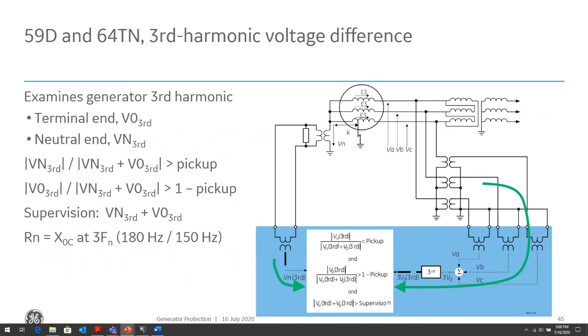So this allows us to be able to set the element without the concerns about the operating points of the generator that we talked about with the 27TN, because we're looking at voltage differential, we're not looking at an under voltage condition. So if we're in a part of the region where the third harmonic voltage is very low or non-existent, then we will not operate because the difference between the two terminals will be very low regardless.